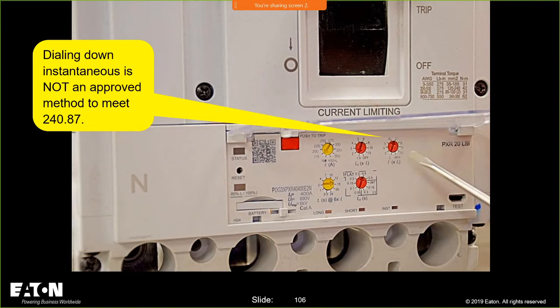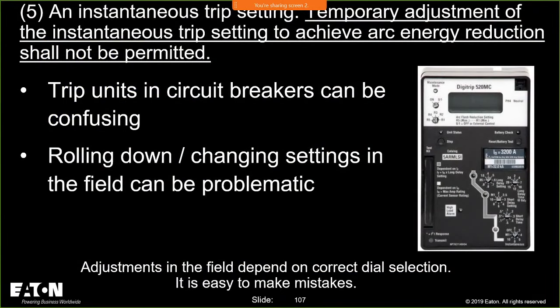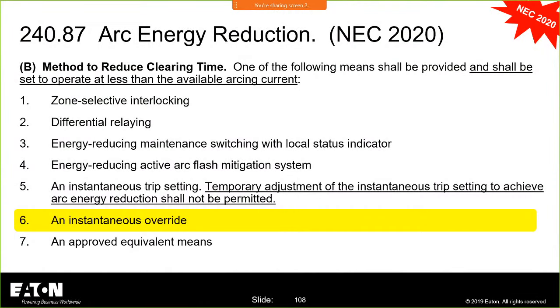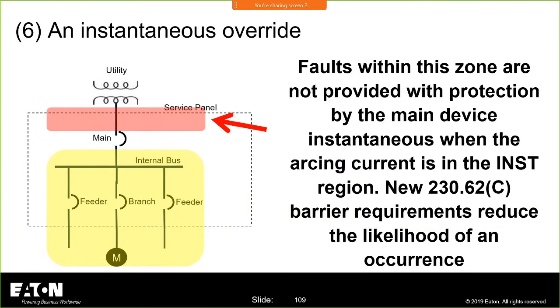It would be ungood. All the terminology, how do you know which one of these buttons is instantaneous versus short time delay versus long time delay? Every manufacturer is going to be different. Okay. Some trip units are pretty nice. They give you the whole trip curve right on the face, but some of them are digital electronic. You don't want to be modifying these things in the field. Turning a switch on and off does not equate to field adjusting the instantaneous and vice versa. Right. So the instantaneous override, you'll understand what an instantaneous override is if you show up on Thursday.